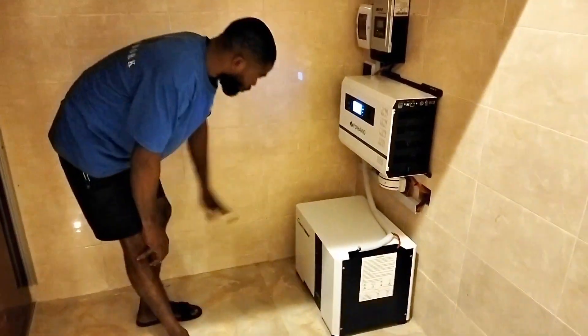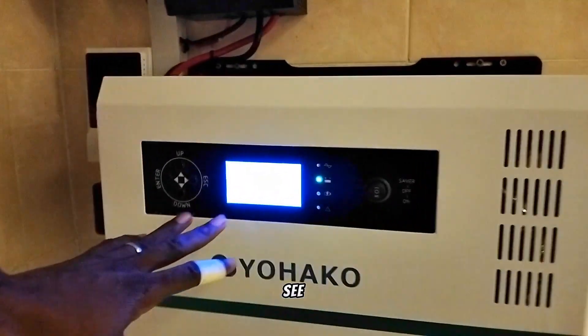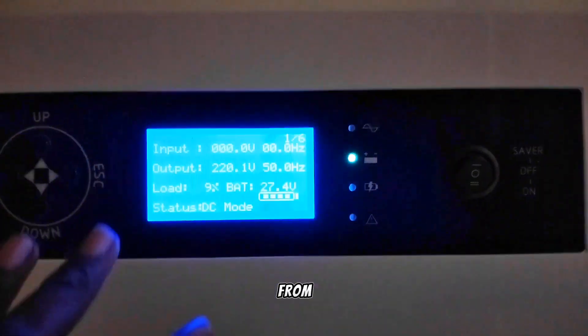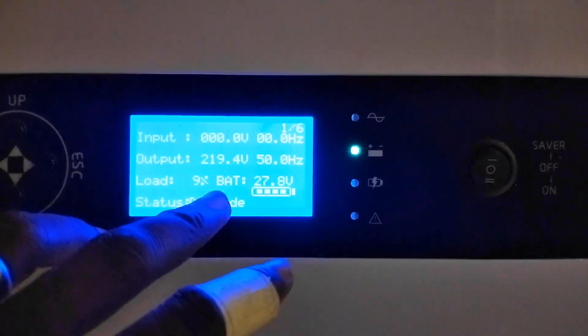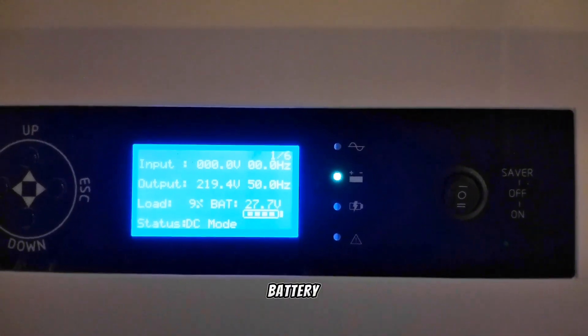This is the full set of the 3.5 kVA solar energy system. There is no grid input right now, so everything you see is working from the inverter. The output is 220 volts, our load is nine percent, battery is at 27.8 volts, and the status is DC mode — meaning we are consuming from the battery.